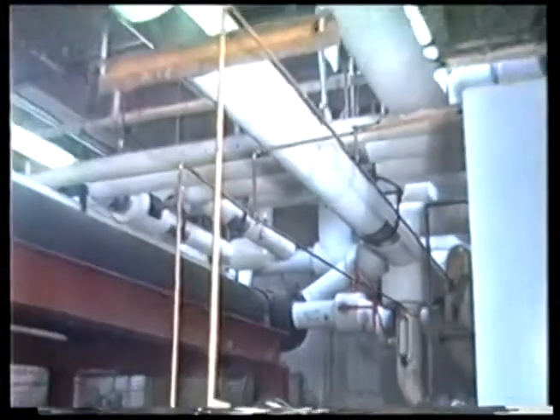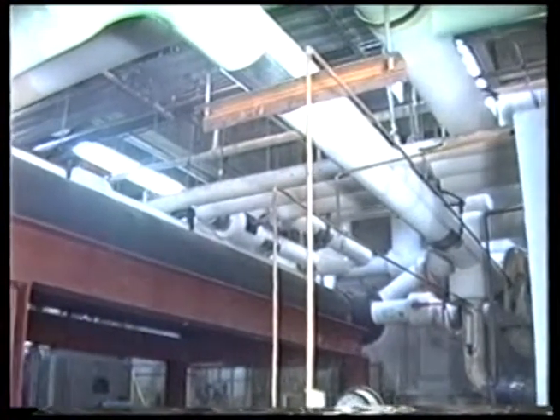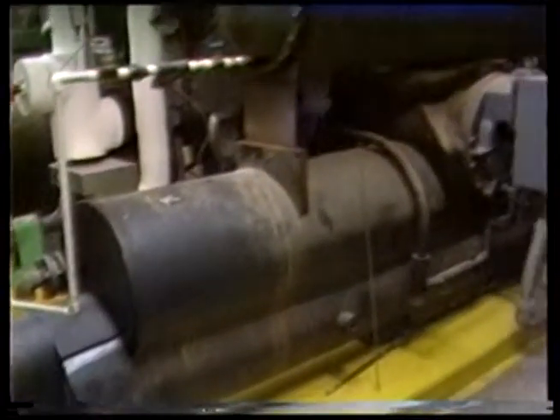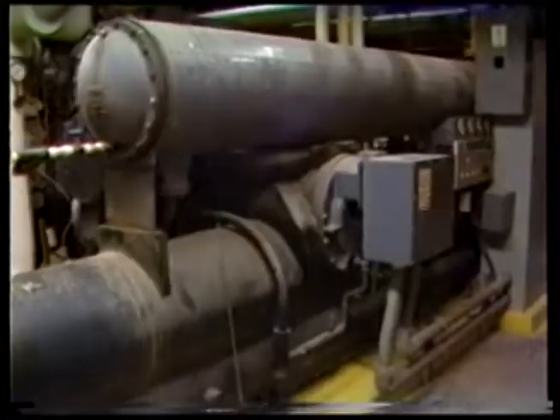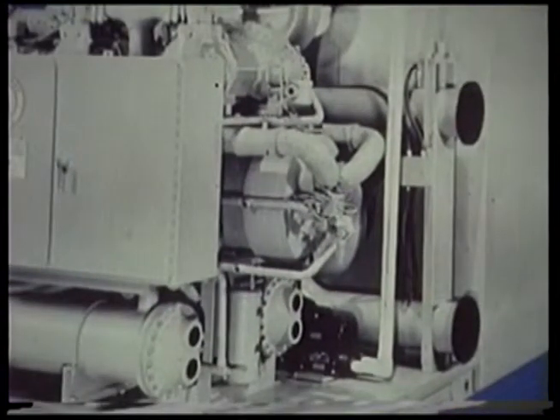When water must be used in the system cooling circuit, BAC will furnish either the high-K shell and tube type or a plate and frame type heat exchanger. The condenser is a water-cooled, cleanable shell and tube type. The cooler is a direct expansion shell and tube type. It naturally complies with current ASME codes.